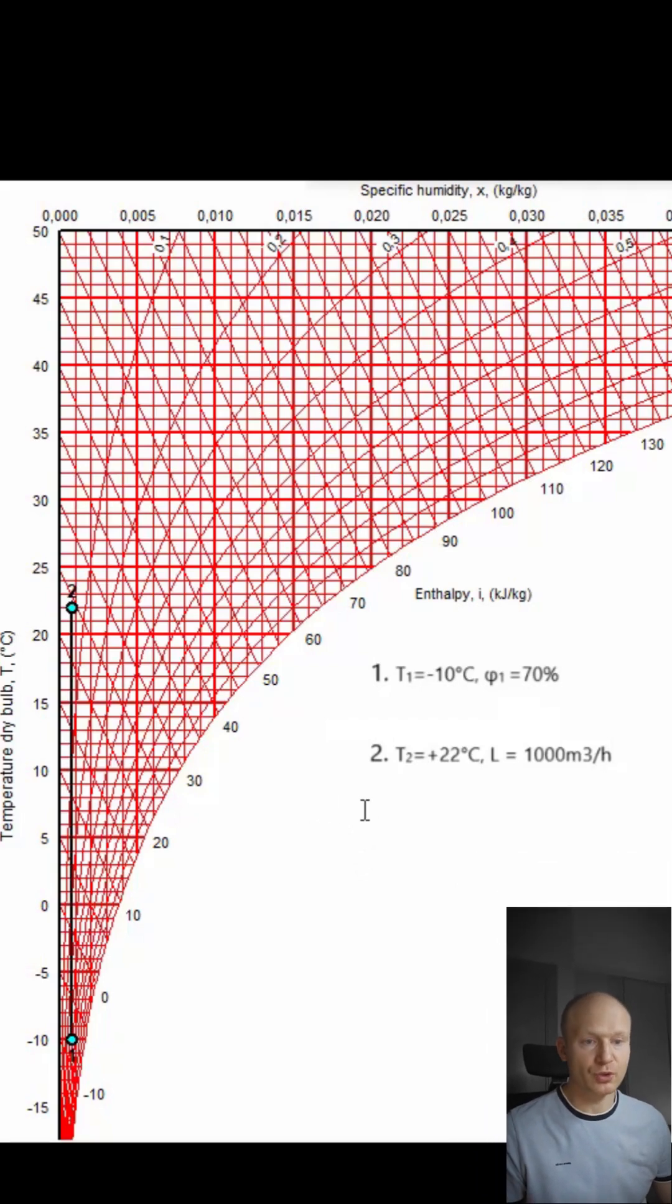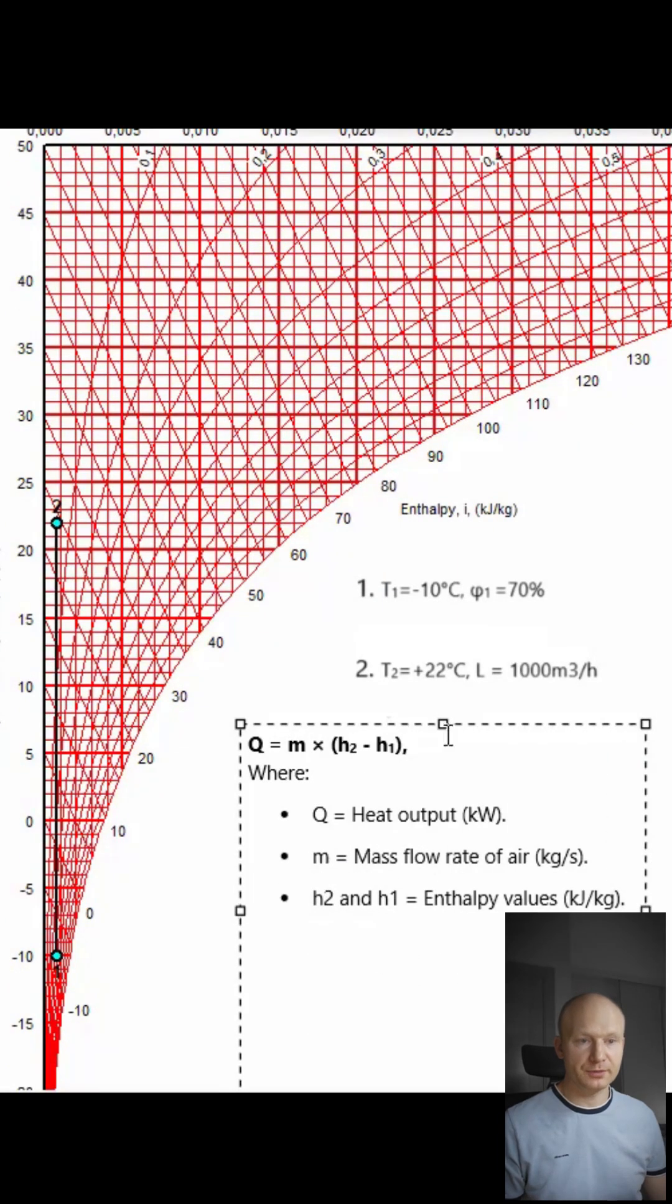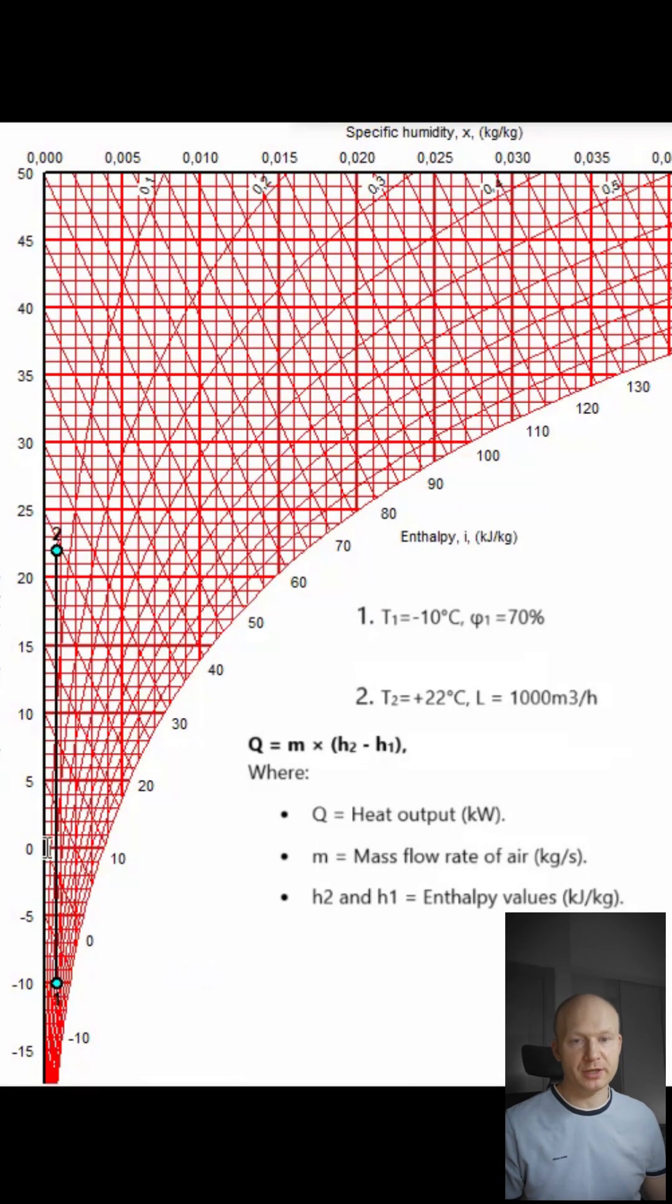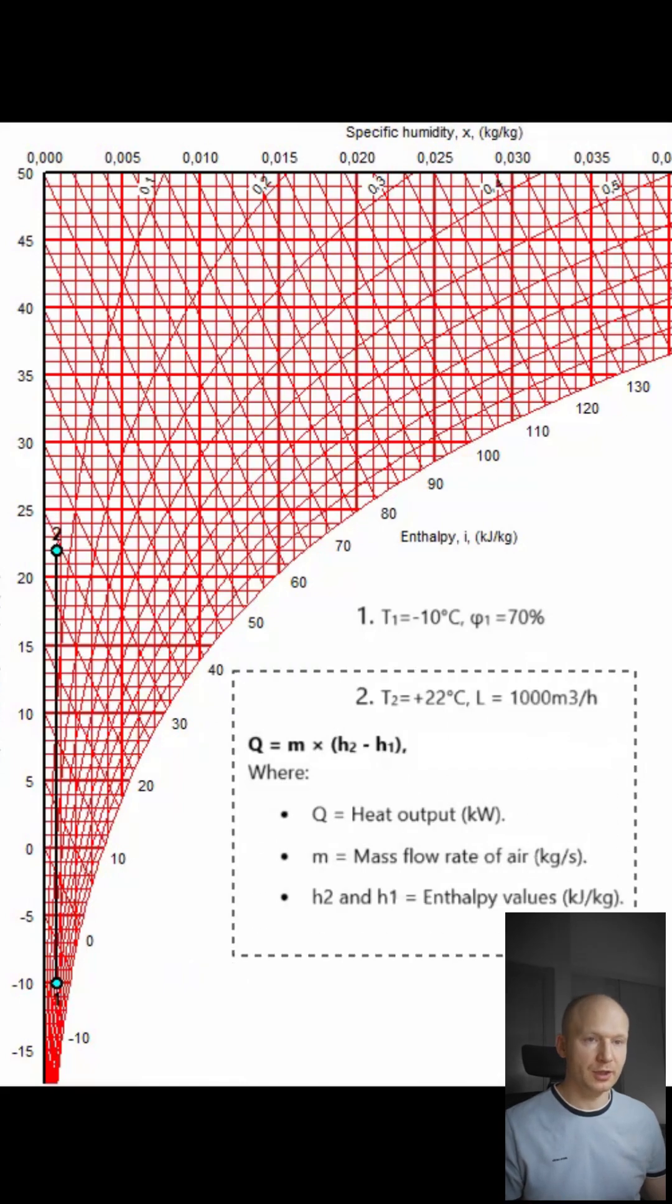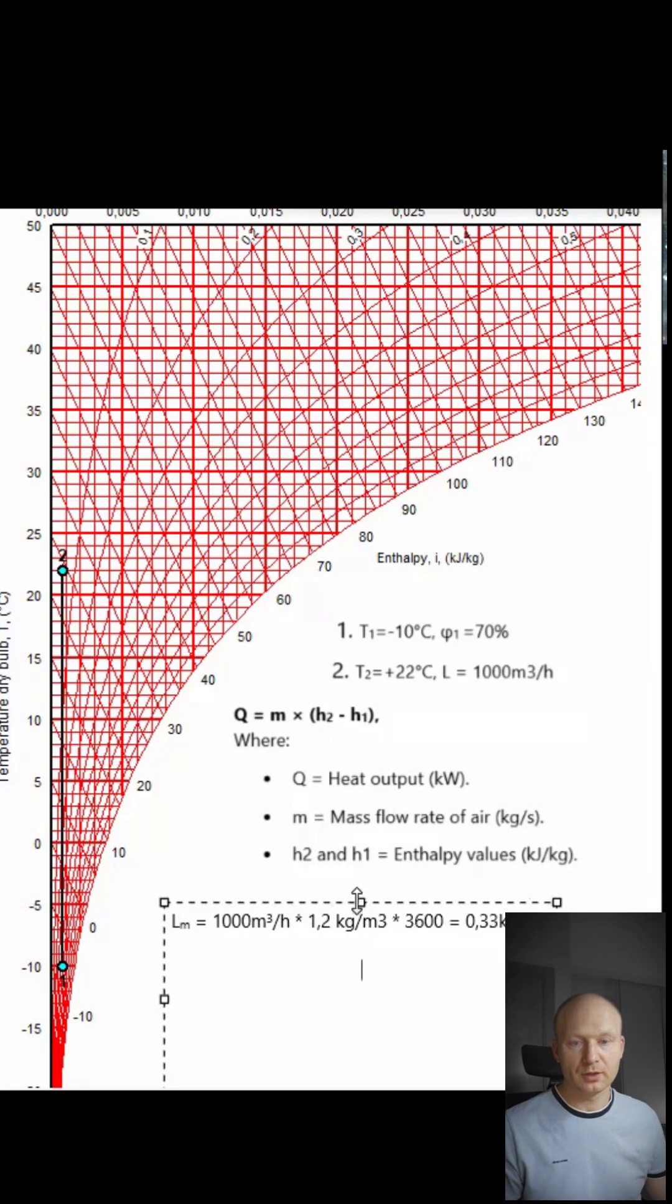The difference between the two enthalpy values is the magic ingredient. Next, apply this simple formula where Q is heat output in kilowatts, M is mass flow in kilograms per second. We'll need to transfer the volume flow to the mass flow. H1 and H2 are enthalpy at point 1 and point 2 in kilojoules per kilogram. Just plug and play.